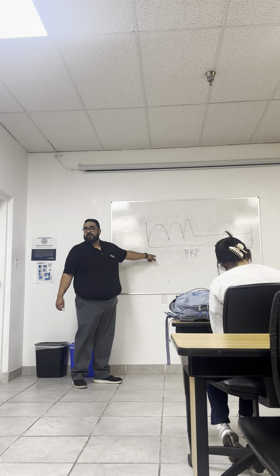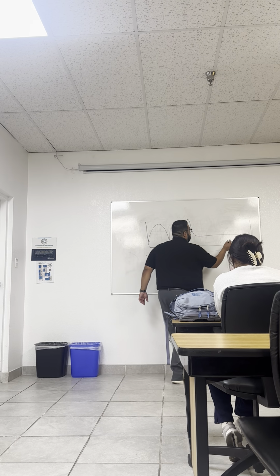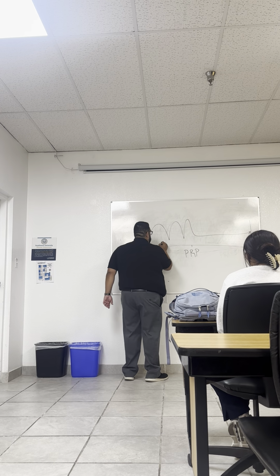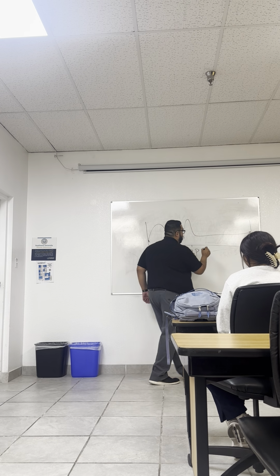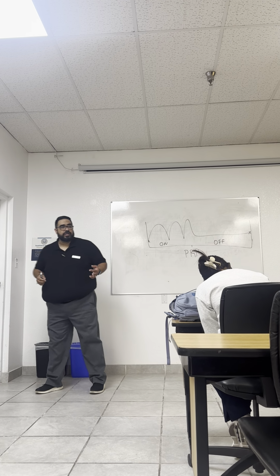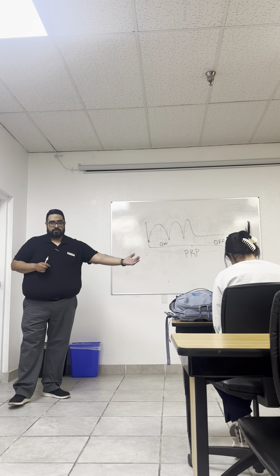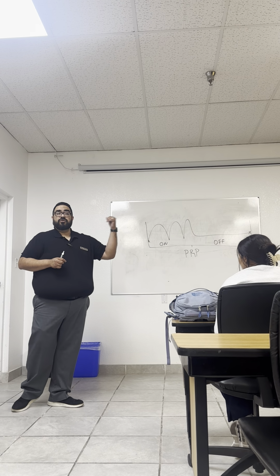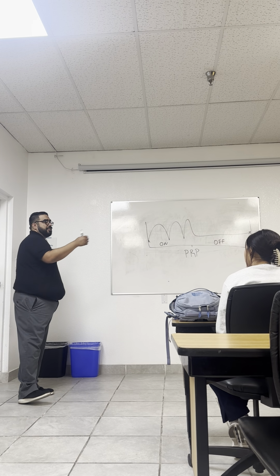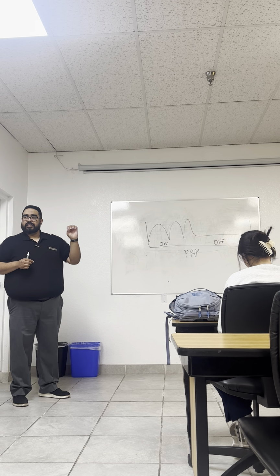And what does our PRP measure? The start of one pulse to the start of the following pulse, or one on time and one off time. Why do we need an on and an off time? To give the machine time to analyze the data? Not analyze, to receive the echo. It's going to send a pulse, that pulse is going to travel, and as that sound is traveling through all these different tissues, it's sending back echoes. So it's listening to get those echoes back.